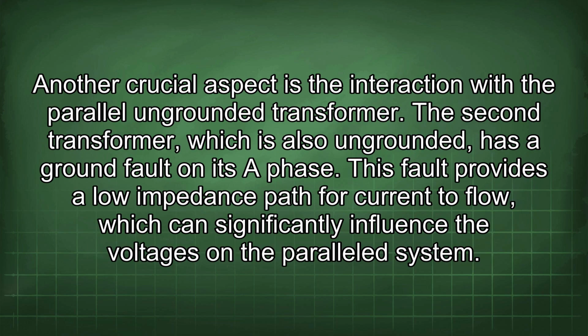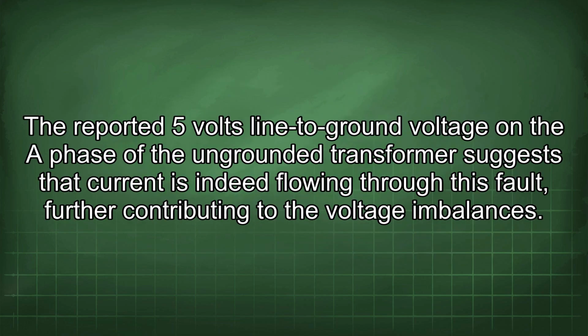Another crucial aspect is the interaction with a parallel ungrounded transformer. The second transformer, which is also ungrounded, has a ground fault on its A phase. This fault provides a low impedance path for current to flow, which can significantly influence the voltages on the paralleled system. The reported 5 volts line to ground voltage on the A phase of the ungrounded transformer suggests that current is indeed flowing through this fault, further contributing to the voltage imbalances.